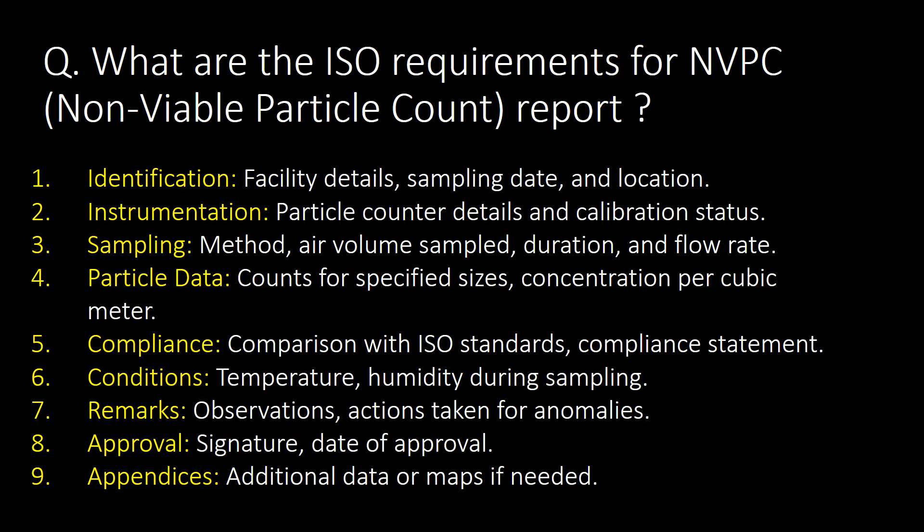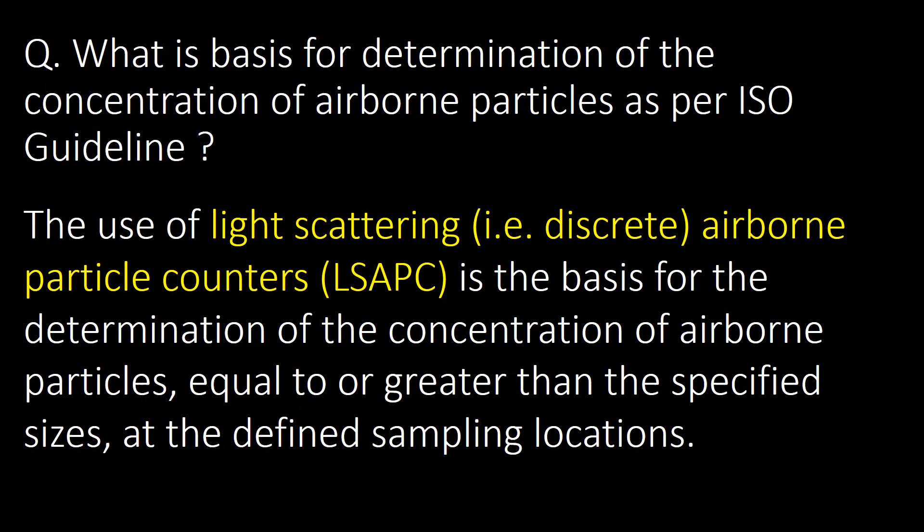What are the ISO requirements for a non-viable particle count (NVPC) report? First: identification. Second: instrumentation, which includes particle counter details and calibration status. Third: sampling, which includes sampling method, air volume sampled, duration, and flow rate. Fourth: particle data, which includes counts for specified sizes and concentration per cubic meter. Fifth: compliance. Sixth: conditions such as temperature and humidity during sampling. Seventh: remarks. Eighth: approval. Ninth: appendices.